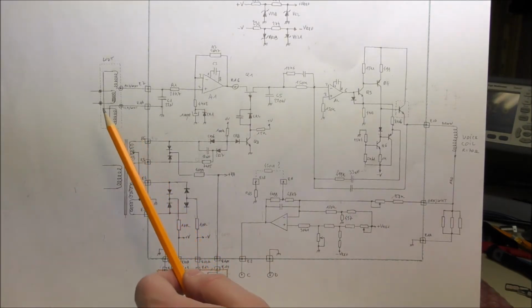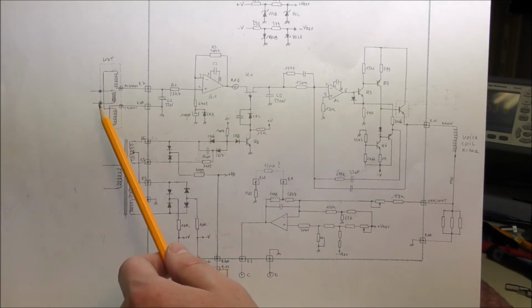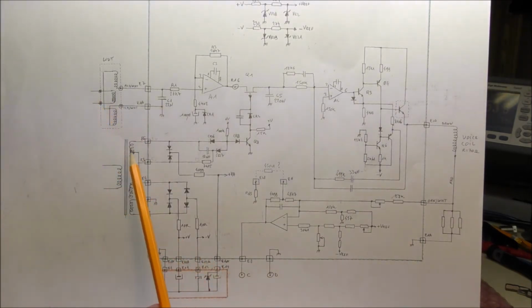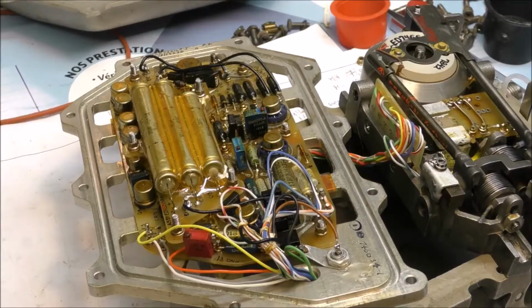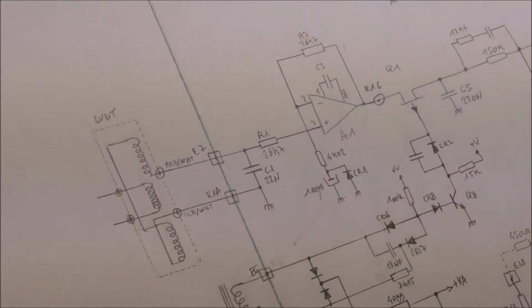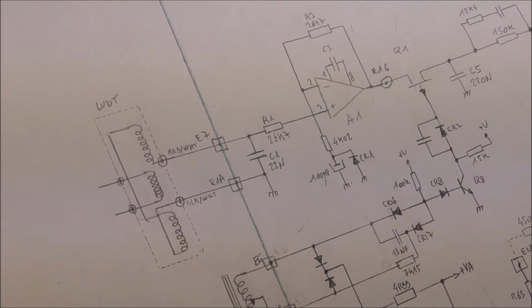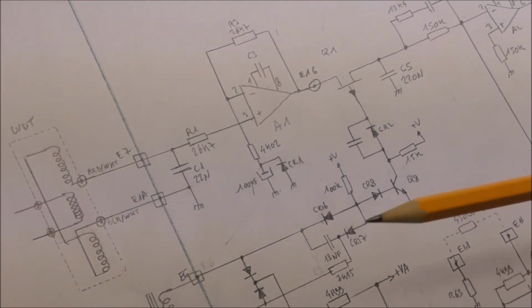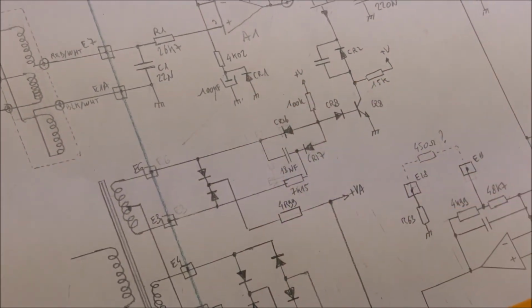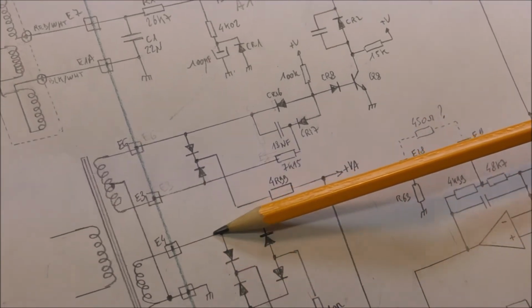I don't know where is connected the excitation coil of the LVDT sensor. It is difficult to follow the wires. It is probably connected to the same secondary voltage than the phase detector. So let's see now if we can make it work. First I will search for the power supply input. For that purpose I will do as usual. I will connect an AC generator, for example on this secondary here.